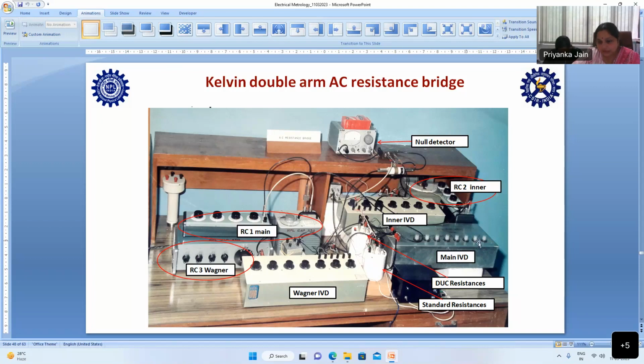If you look at the digits of these IVDs, if it is in the 6th place, it is the 10 ppm place. If it is in the 7th place, it is the 1 ppm place, and then the 0.1 ppm place. So we can balance these bridges up to 0.1 ppm precision. The standards measured through this Kelvin double arm bridge are very precise, and the uncertainties of the 1 ohm to 1 mega ohm standard resistors are in the order of 2 ppm to 100 ppm. So this is our Kelvin double arm DC resistance bridge.